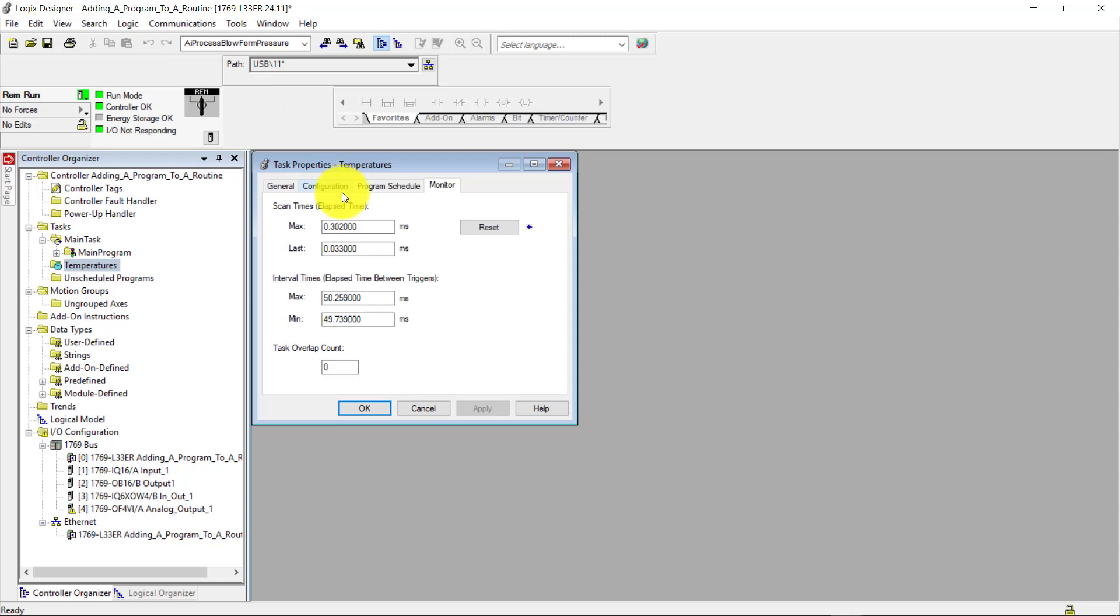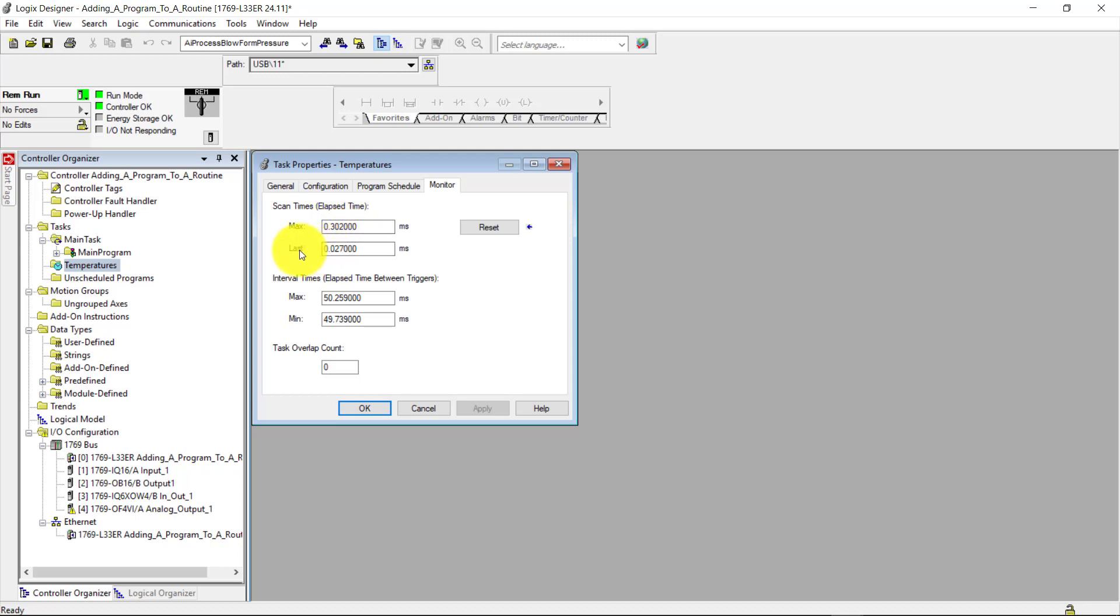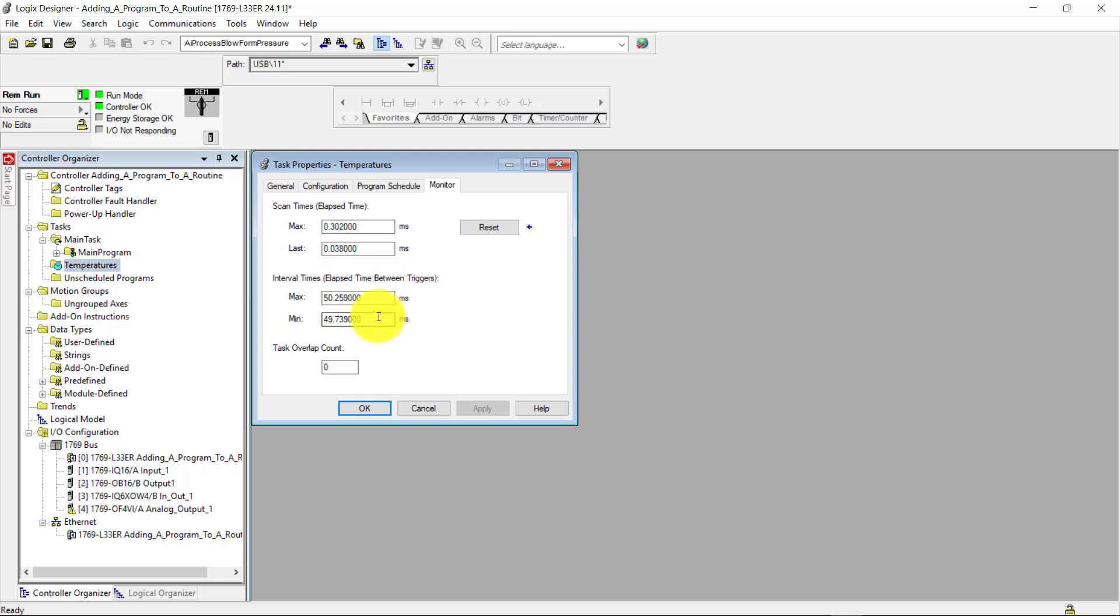Online, I can see the actual milliseconds that this task is taking, which is the maximum here. And I also have the last scan right here. And I also have the interval, the elapsed time between the triggers, which is the max here, and also the minimum here.